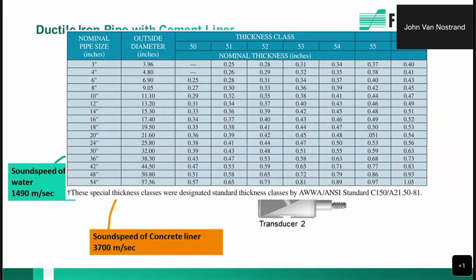Well, when you look at ductile iron pipe, which is very common in the water market, as we know, there are a variety of thickness classes. And if you're looking at from class 50 to class 56, how do we know that we're on the right pipe or we have it programmed correctly? For example, on a 16-inch class 50, you have a wall thickness of 0.34, where on a class 56, it's 0.52. So what do we put in? I usually start right in the middle. I would go with the 0.43, and then I look at the sound speed of the media.